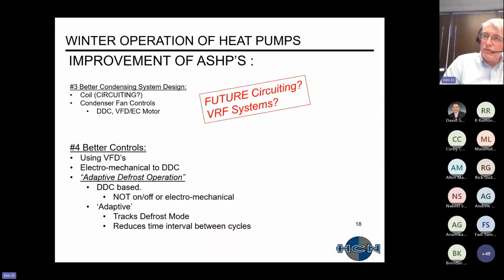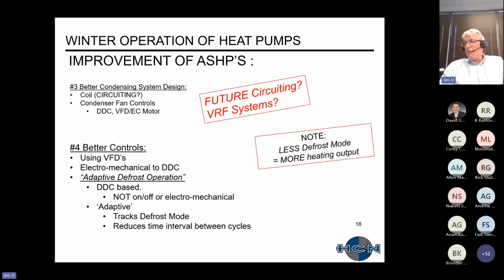And then lastly is just better controls, as I said, with the VFD, changing from electrical-mechanical to direct digital controls. And another term that's come up the last couple of years is adaptive defrost operation. So this is once again using more accurate DDC controls. Instead of just the defrost cycle running for 10 minutes, they actually track how long the defrost cycle runs. And if they realize that over time the defrost ends up cleaning itself or resetting itself in 6 minutes or 8 minutes, the controller will reduce that time frame to reduce the length of the defrost. Once again, I just want to emphasize that when you're in defrost mode, you're not heating, so less defrost mode means more heating output.